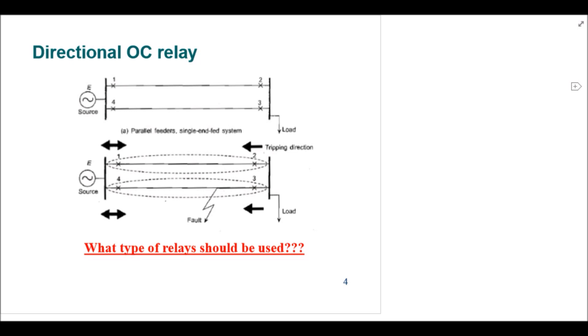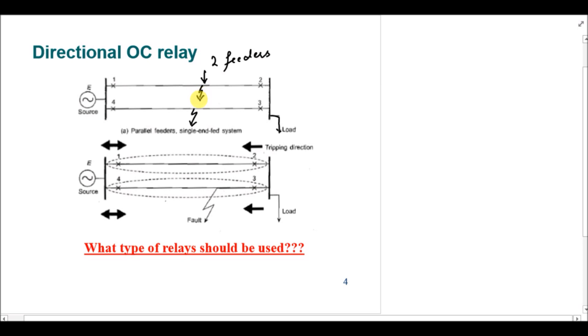Another example is when we have a load attached to a bus bar that is fed through two parallel feeders. In this case, a fault can occur in either line, and there is a possibility that both lines will trip if there is a fault in either one. So in this case as well we require directional relays. We will use directional overcurrent relays at the circuit breakers which will have bi-directional flow of power in case of a fault.